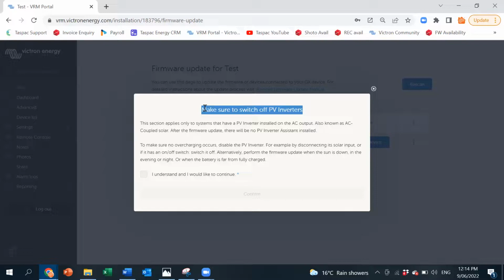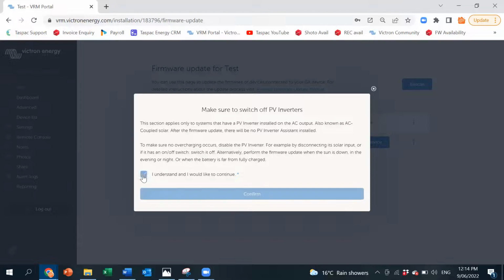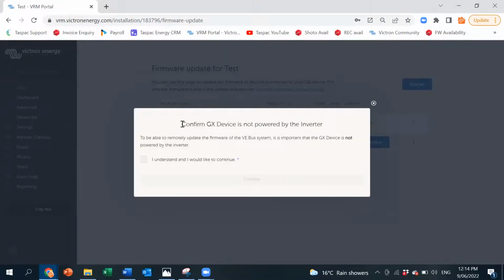So it's possible that it will overcharge the battery or cause a shutdown on the site. So you've got to understand that, and you will turn the PV inverter off or ask the customer to turn it off. Continue. And the second to last thing is, it's not powered by the inverter.